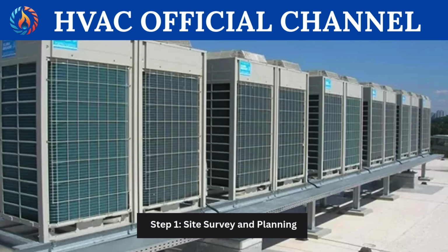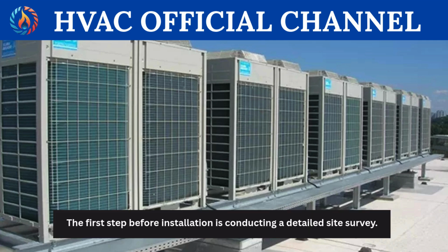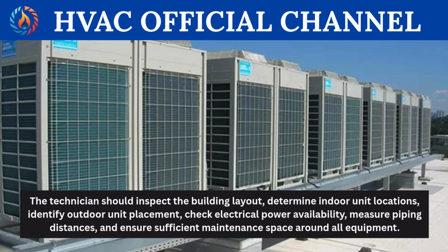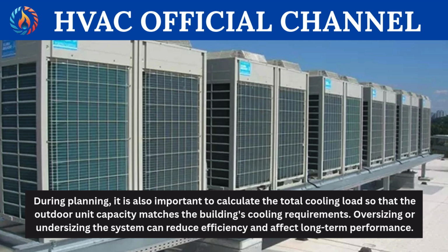Step 1. Site survey and planning. The first step before installation is conducting a detailed site survey. The technician should inspect the building layout, determine indoor unit locations, identify outdoor unit placement, check electrical power availability, measure piping distances, and ensure sufficient maintenance space around all equipment. During planning, it is also important to calculate the total cooling load so that the outdoor unit capacity matches the building's cooling requirements. Oversizing or undersizing the system can reduce efficiency and affect long-term performance.